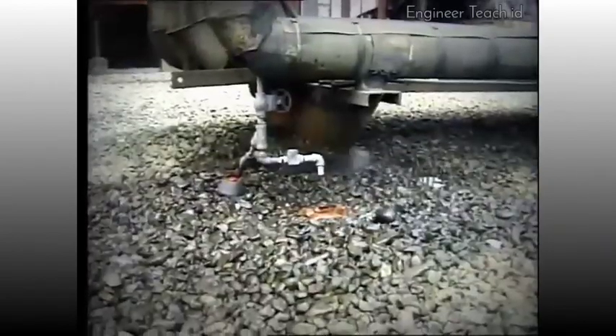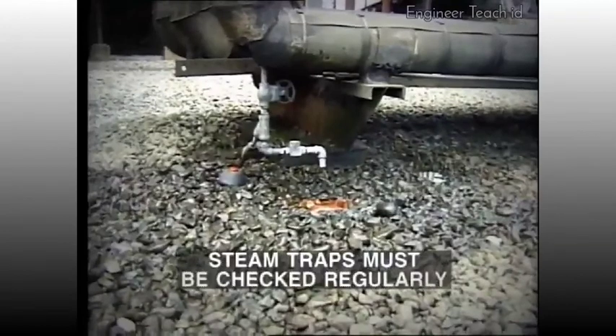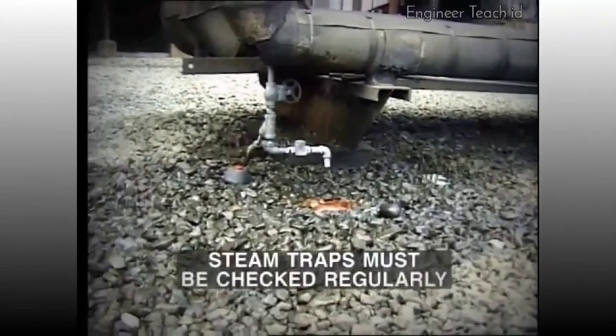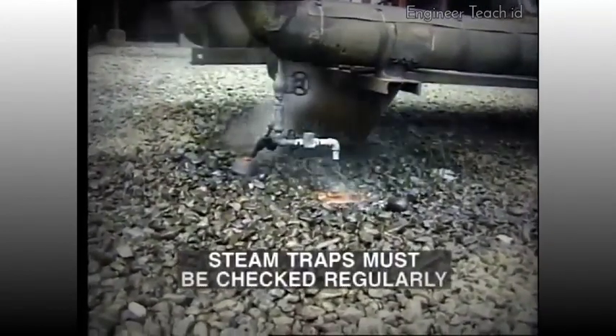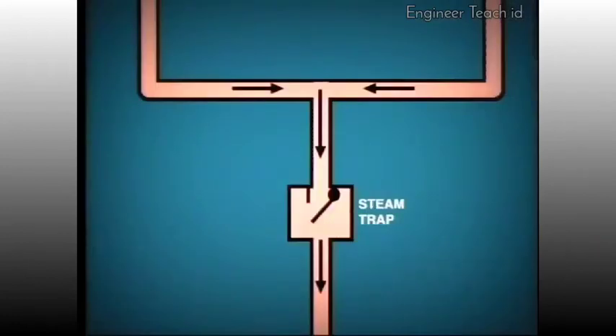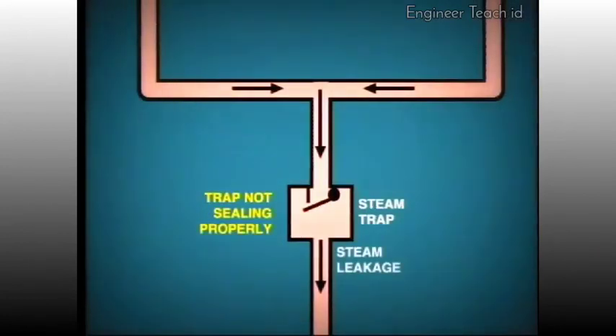The operator should regularly check that the steam traps are functioning correctly, that is, to discharge condensate in regular bursts. If the steam trap is not sealing properly, it will pass steam continuously and so be a source of considerable waste.